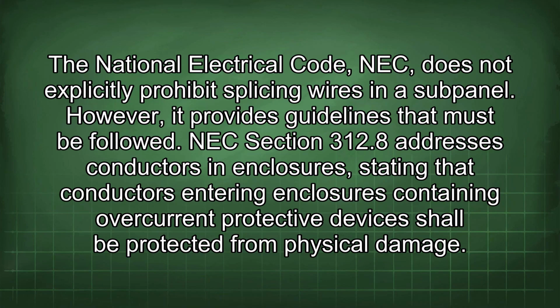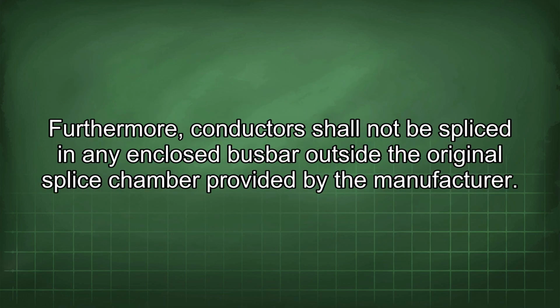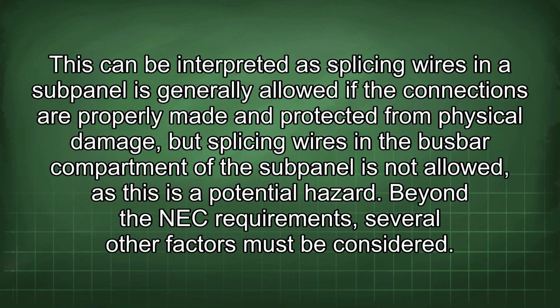The National Electrical Code (NEC) does not explicitly prohibit splicing wires in a subpanel. However, it provides guidelines that must be followed. NEC Section 312.8 addresses conductors in enclosures, stating that conductors entering enclosures containing overcurrent protective devices shall be protected from physical damage. Furthermore, conductors shall not be spliced in any enclosed busbar outside the original splice chamber provided by the manufacturer.